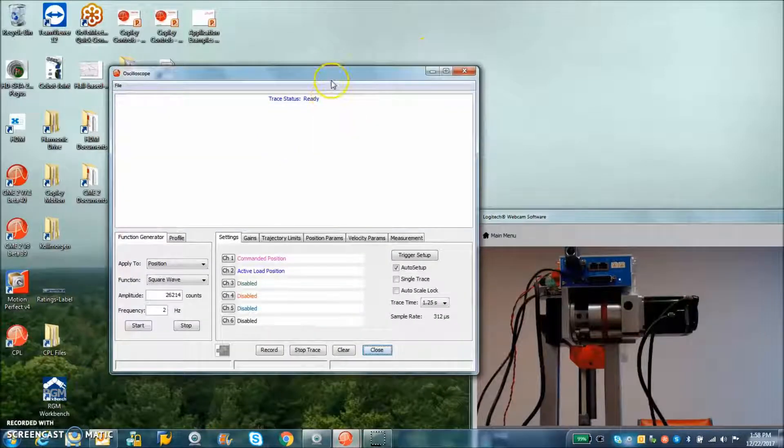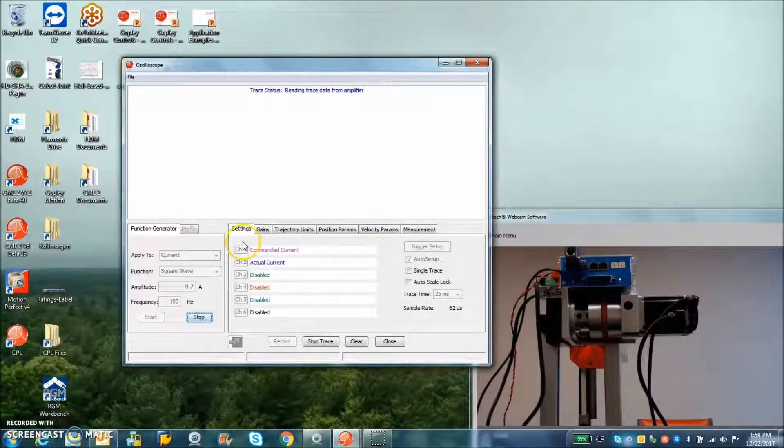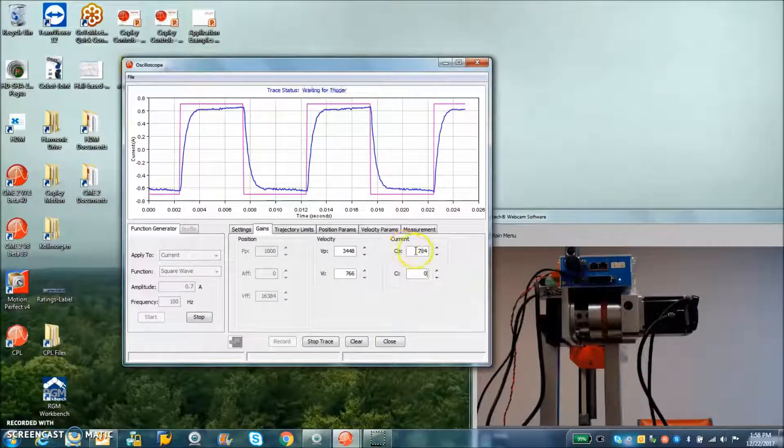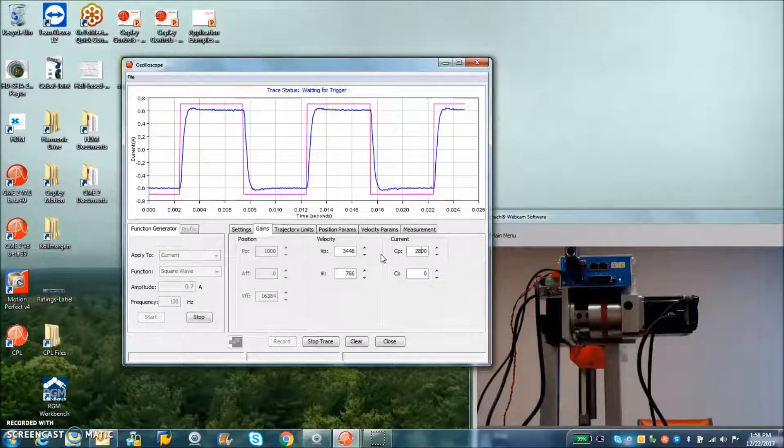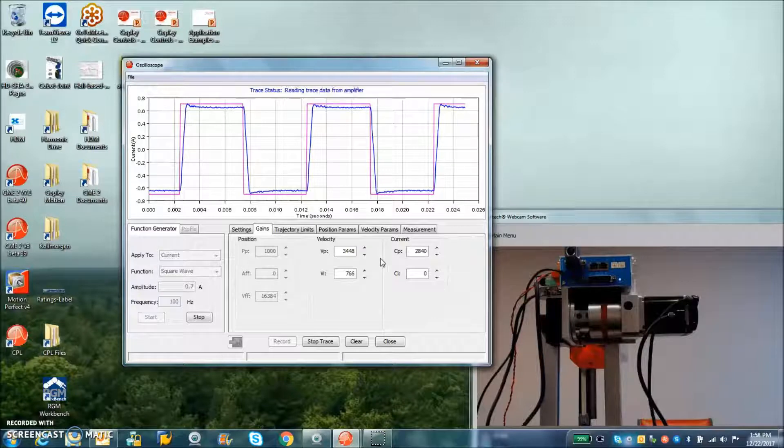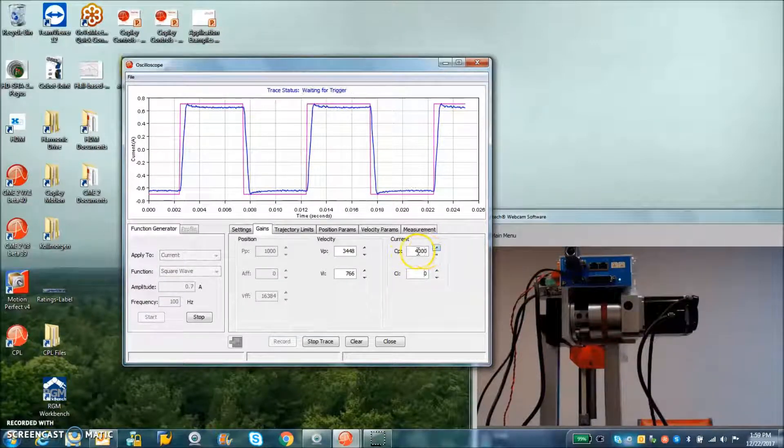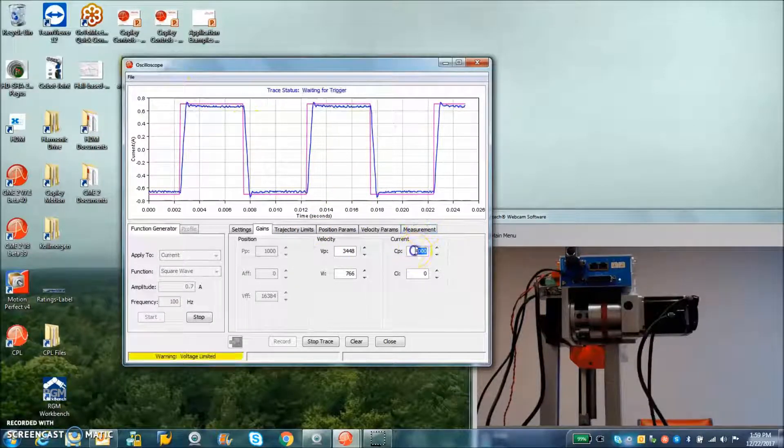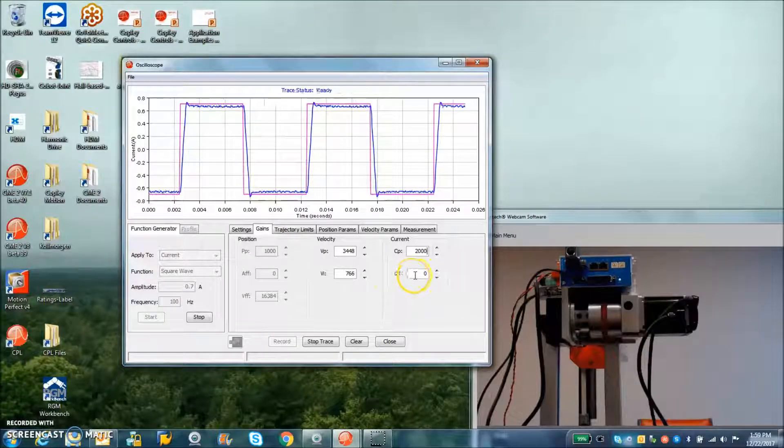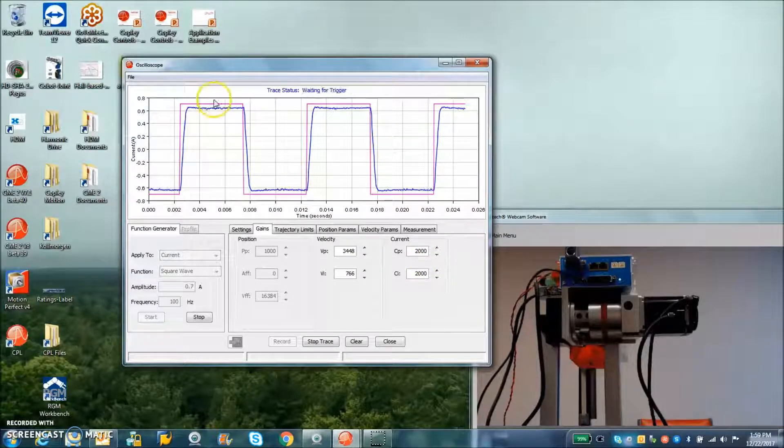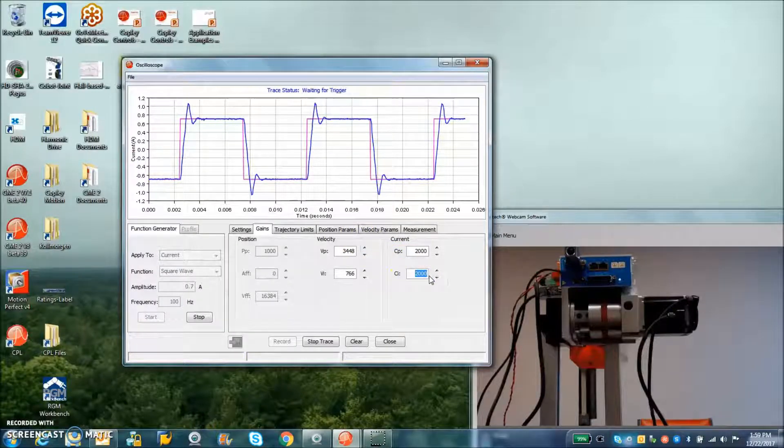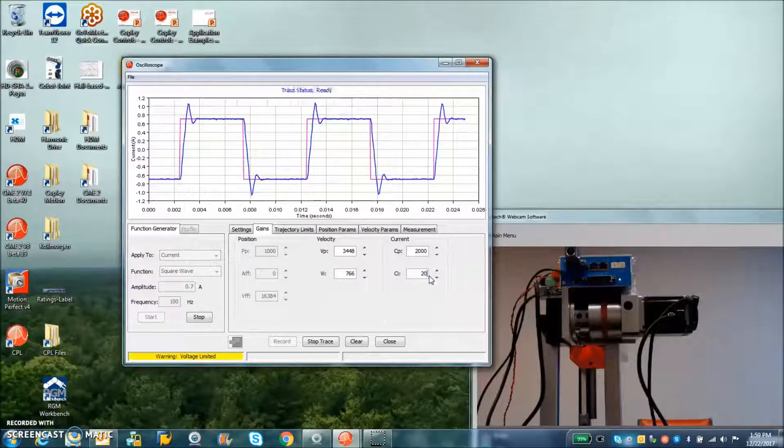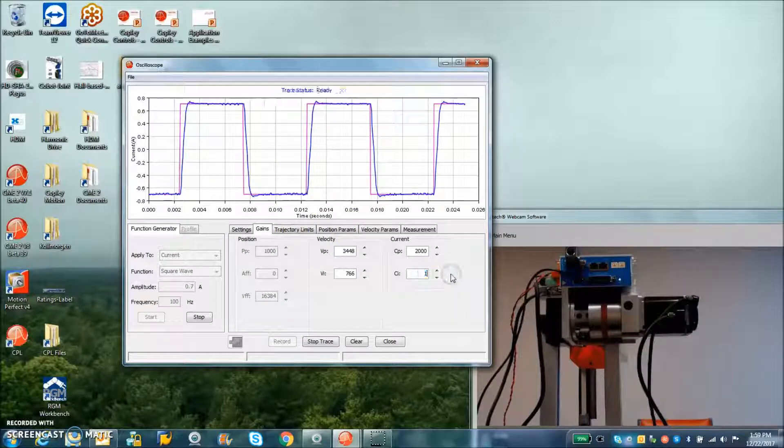So normally when I tune the current loop, I apply a current auto setup checkbox, hit start, small signal and set my integral to zero. Let's go for double the current loop gain. I'm looking for the point at which I get an overshoot. 4,000. So I'm starting to get a little peaking here. So there's a little overshoot. So I'm just going to cut this number in half. Yeah, it's a large inductance. I got a slew rate limit. If the integral term is too high, you'll get integral wind up and overshoot. You can see the slew rate limit there. I'm running this 8 millihenry with 0.6 volts. So it's a little droopy there.